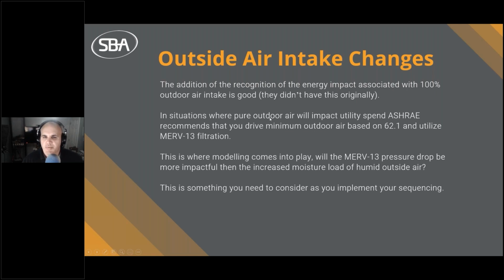Now, in situations where pure outdoor air, like in Louisiana or Florida, is going to cause a lot of utility spend impacts, then ASHRAE is going to recommend you drive outdoor air based on 62.1 and utilize MERV 13 filtration. Now, this is where, in my opinion, some modeling is going to come into play, or some calculations. You have to ask yourself, will the MERV 13 pressure drop be more impactful than the increased moisture load of humid outside air?